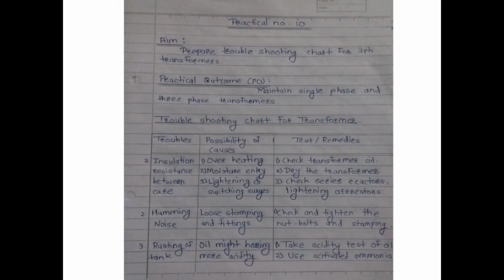Then the tests and remedies are: check the transformer oil, second, dry the transformer, and for lightning and switching surges, the remedies are to check the series reactors and lightning arrestor. Then second trouble is humming noise. Possible causes are loose stamping and fittings. So the tests and remedies are to check and tighten the nuts, bolts and stamping.